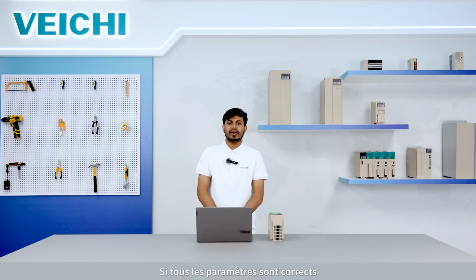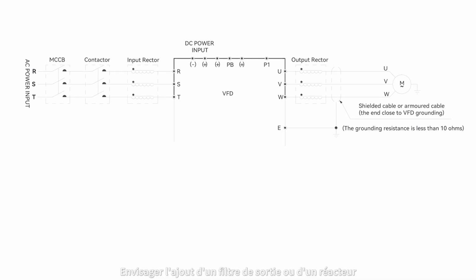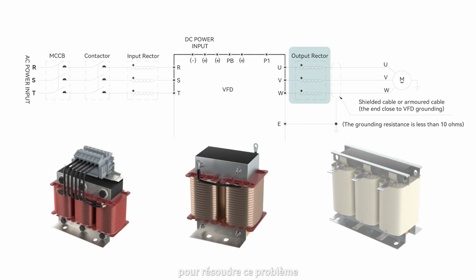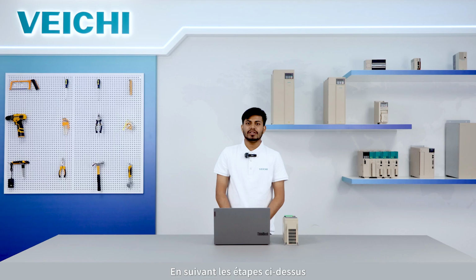Inverter output cable too long. If all parameters are correct, the issue might be due to the motor output cable is too long. Consider adding a output filter or reactor to resolve this issue. By following this step, you should be able to troubleshoot. If issues persist, consult the manual or seek for further assistance. Thanks for watching.